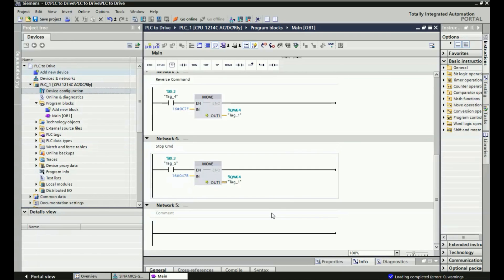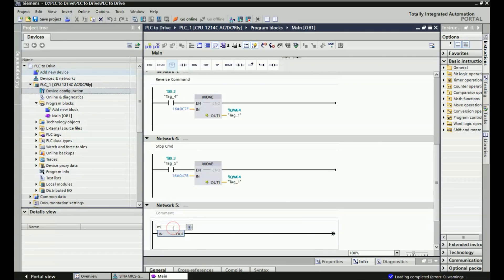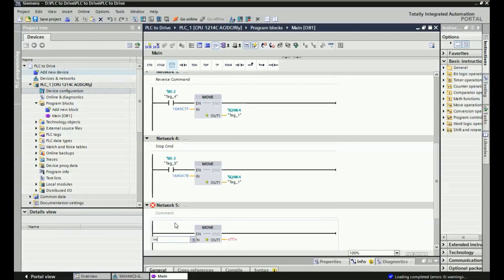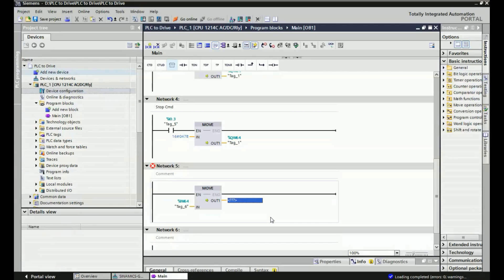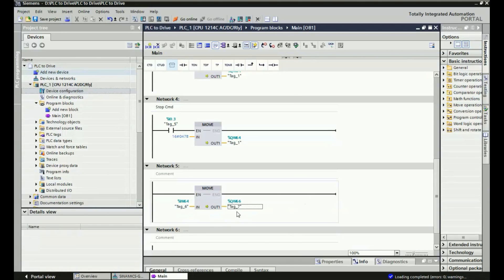If you want to vary the speed, we can use the second control status word QW66. Here I will use a move block and assign an analog input from the PLC. We are getting 2 analog inputs on the CPU 1214C AC/DC relay. I will assign the first analog input IW64, and that analog value will be moved into the second control status word QW66. So I can vary the motor speed from this analog set point. For that we will add 2 parameters in this drive. After assigning this run command ON, we will download this program.